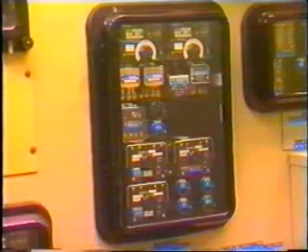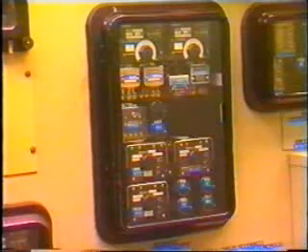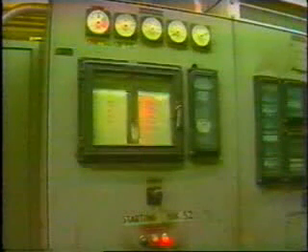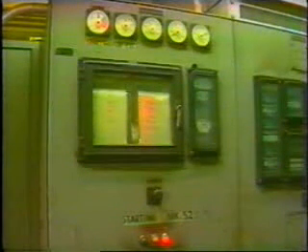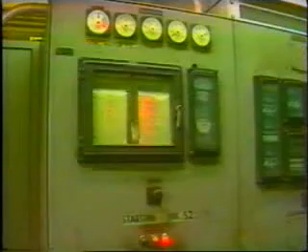You will remember in an earlier tape that we discussed special protection required for the generator during startup. Startup protection for the synchronous motor is similar. It's usually provided by the motor manufacturer and includes protection for starting, switching in the field, and synchronizing. Okay, so much for synchronous motors. Now, at this point, let's briefly summarize the main features of motor protection.